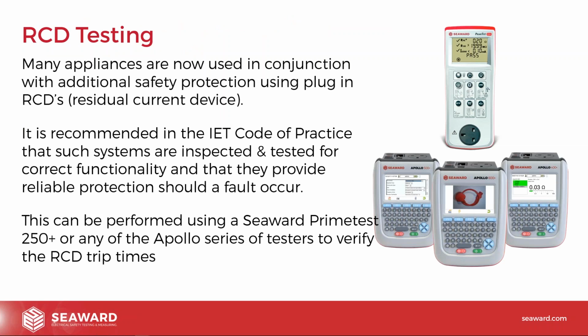So RCD testing is another important part of testing, just to make you aware of. And in the code of practice now, we are required to actually check things like the tripping times. It used to be we just press the test button on the RCD and there we go, but now we are required to actually carry out the tripping time test. So things like the Primetest 250+ have got the RCD testing. Obviously, the Apollos have got the ability to carry out RCD trip time tests in there. So if you are testing equipment that has got RCDs, or you are coming across RCDs, obviously just think about that when you're selecting the right tester to get, that you can actually perform the RCD tests.